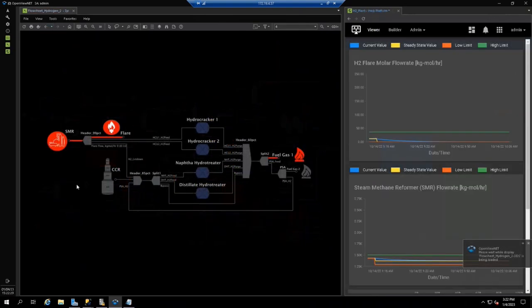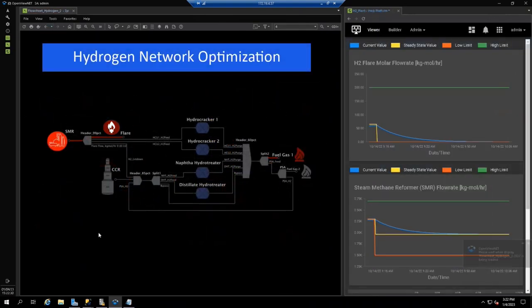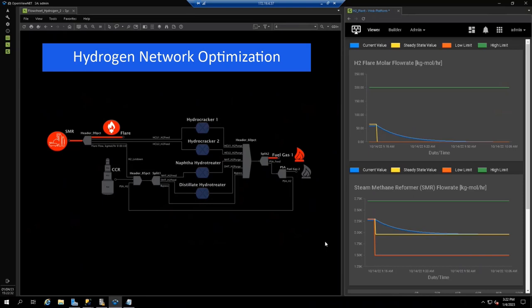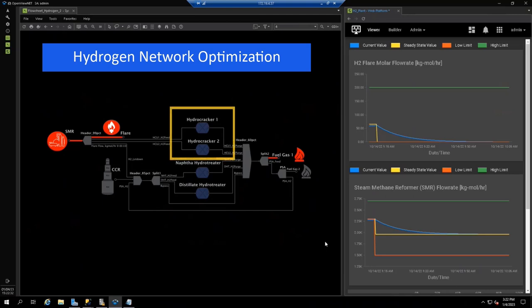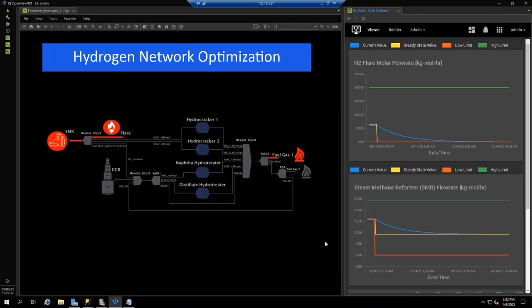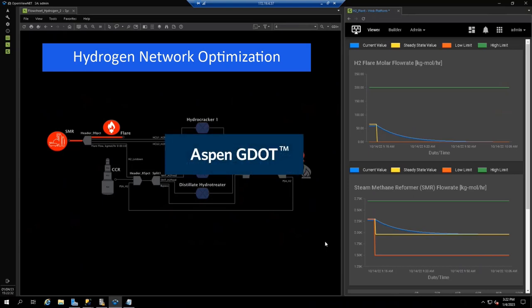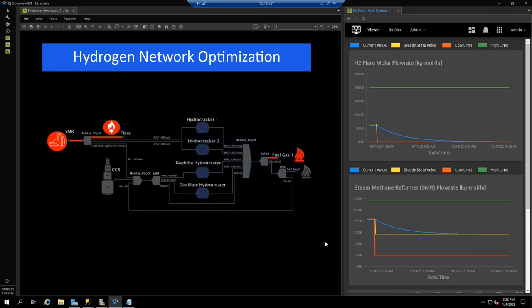Finally, we discover excessive hydrogen flaring at a rate of 60 kgmol per hour in the steam methane reformer, or SMR, hydrogen unit, which contributed to CO2 emissions that are higher than planned. In this network, the hydrogen producers are the SMR and catalytic reformer, while the consumers are two hydrocrackers and two hydrotreaters. Those four major units are not being optimized. With a dynamic optimizer available in Aspen GDOT, the manual system is converted to auto by enabling dynamic optimization for the hydrogen envelope.